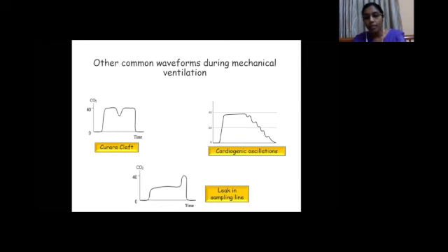During the early phase, in a side stream monitor, a pump aspirates air for analysis. So if there's a leak in the sampling line, during the initial phases there is a lot of entrainment of ambient air, which dilutes the carbon dioxide. As the circuit pressure builds up, the ambient air entrainment comes down and we get a normal reading.